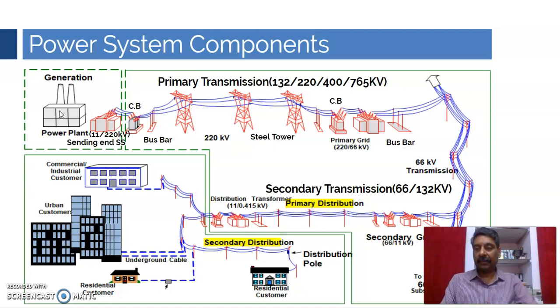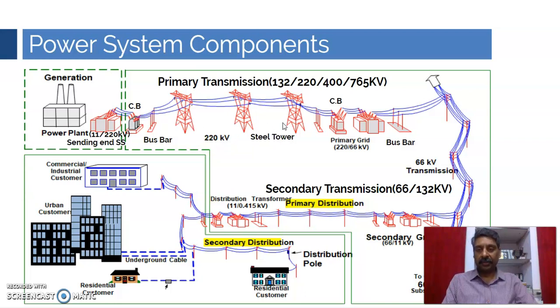Generation at generating stations is at 11 kV. Generators can generate from 11 kV to 33 kV maximum. But if you transmit the same amount of power across transmission lines at the same voltage level, the losses will be much higher and there will be a voltage drop problem. To overcome these two issues — to reduce losses and reduce the voltage drop problem — we step up the voltage. Near the power plant itself, we have a sending-end substation where the voltage is stepped up from 11 kV to 220 kV.